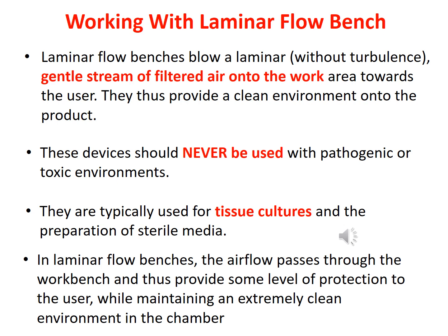While working with laminar flow benches, because in the previous slides I mentioned the flow of air in different cabinets, in this case the air is coming from outside, so you can see it will provide a gentle filtered air onto the worker. Because of that, it will not provide good protection to the worker, and of course it should never be used with pathogens. So never use any pathogenic or toxic materials, because the air passes towards the worker, so it can hurt or be dangerous to the worker.